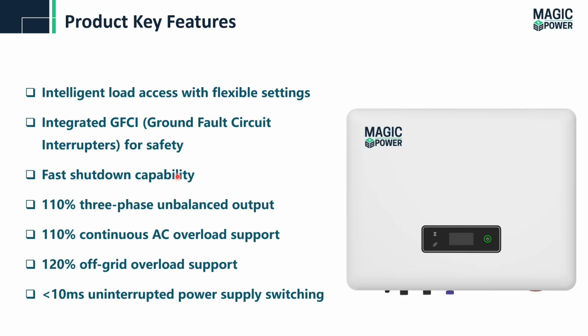Product key features: intelligent load access with flexible settings, integrated ground fault circuit interrupter for safety, and fast shutdown capability. Basically, fast shutdown capability means it comes with an emergency button, so in case of emergency we can use that button to shut down the system. 110% three-phase unbalanced output for phase A, B, and C. 110% continuous AC overloading support for the system, and in case of off-grid, up to 120% overload support. The switching time is less than 10 milliseconds, which is uninterrupted power supply switching.